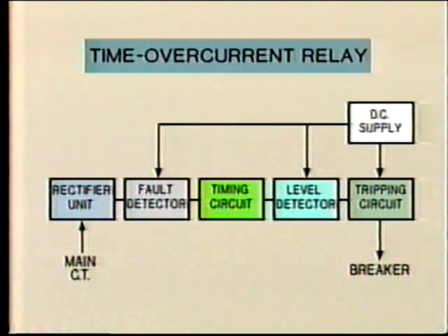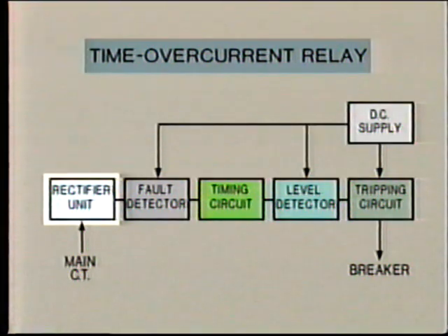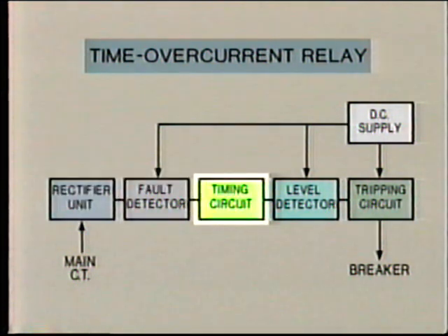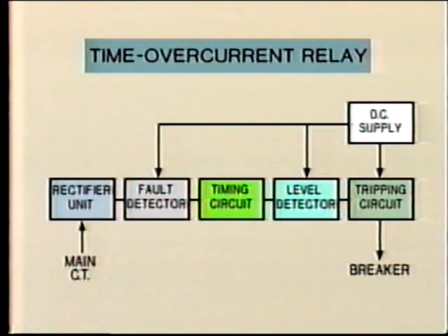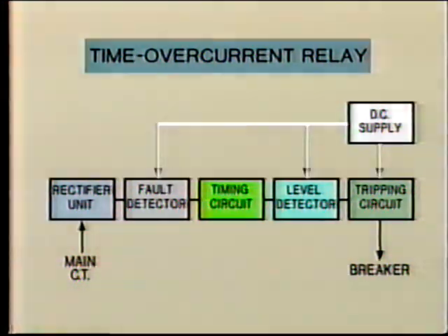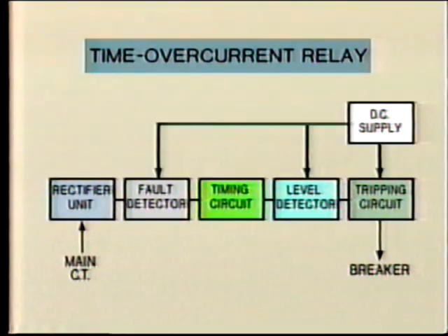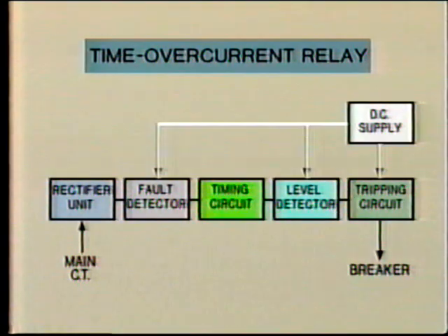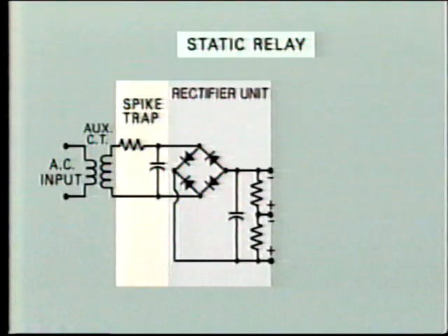The block diagram looks like this. The incoming signal from the CT is rectified and passed into the fault detector, and from here into the timing circuit. When this times out, the trip detector will trigger the tripping circuit. Note that the relay must be provided with DC power to operate the tripping circuit, the trip level detector, and the fault detector. Let's look at these components in more detail.